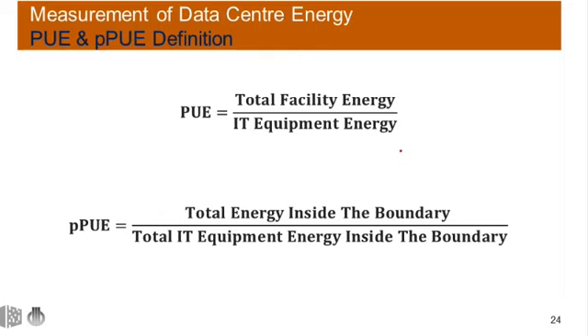PUE does not receive credit for waste heat repurposed. For example, if we were to take waste heat away from the data center and use it to perhaps support some heating or preheating to an adjacent office area, that wouldn't be considered to form part of the PUE metric calculation. However, there is an alternative metric, ERE, which I don't plan to go into any detail today, which does take that into consideration. As I said, PUE is being globally accepted and is widely used across the data center industry as a whole. It's becoming increasingly important as the data center industry focuses on improvements in energy.